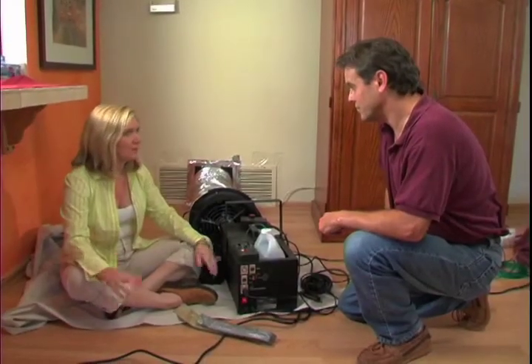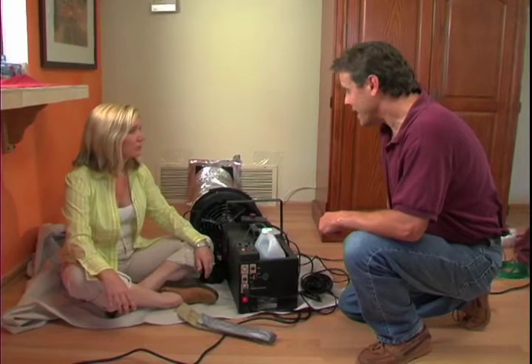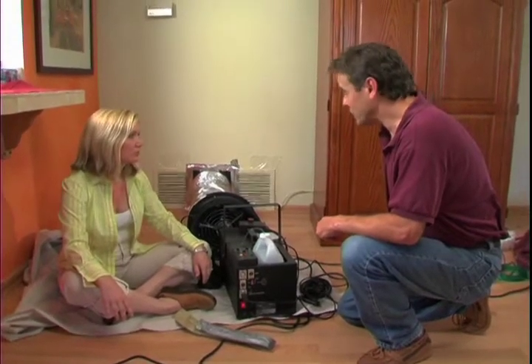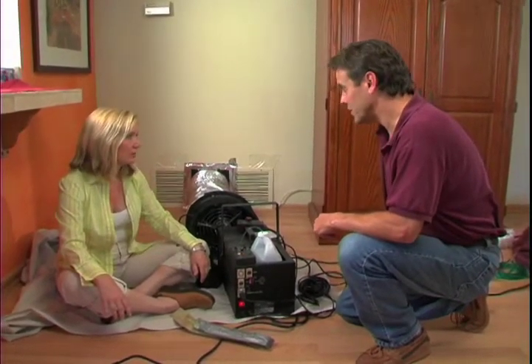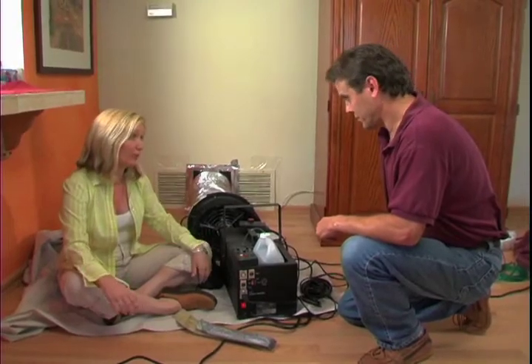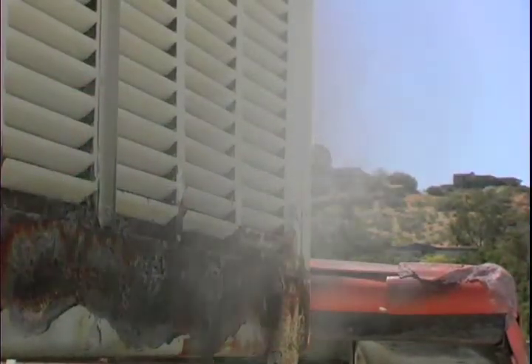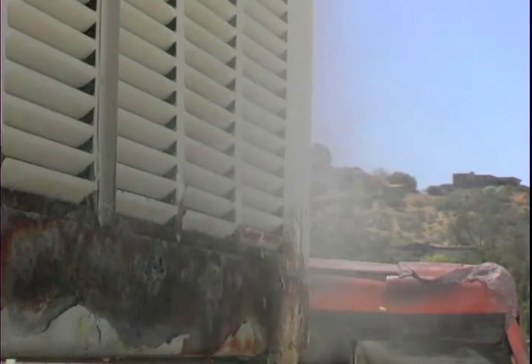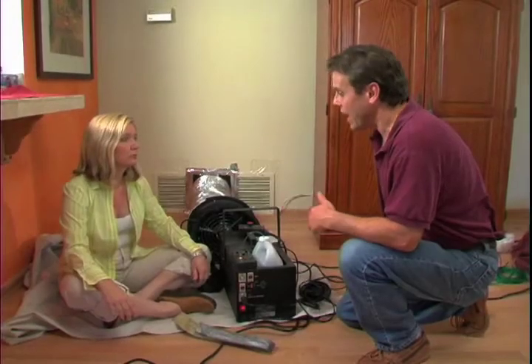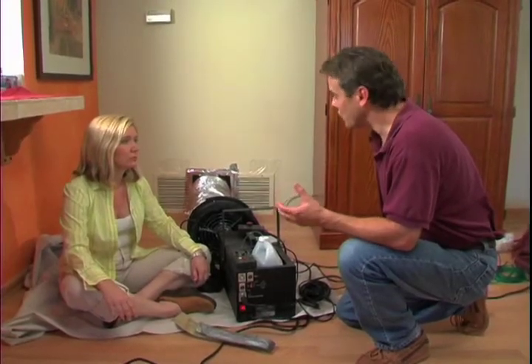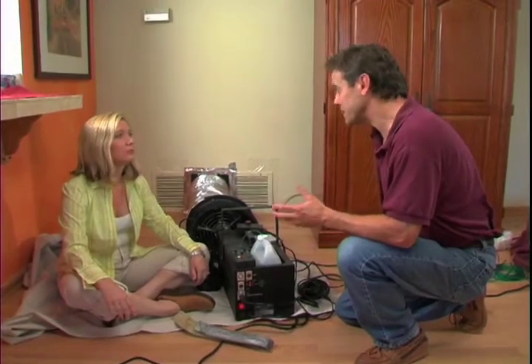So where were some of the leaks that you found in the house? Well, we can't get into the attic to find all the leaks, but we've found some big, obvious ones, such as the evaporative cooler on the roof. In the evap cooler, there's a damper designed to keep the air conditioning air from getting into the evap cooler, and it may have corroded open or be stuck open. We just need to go up and look.